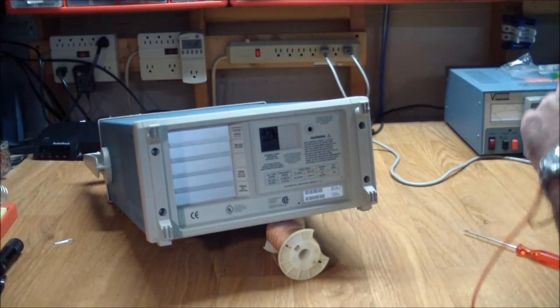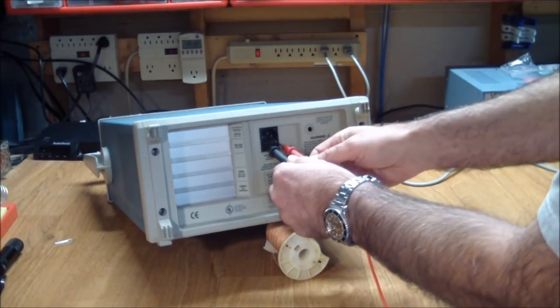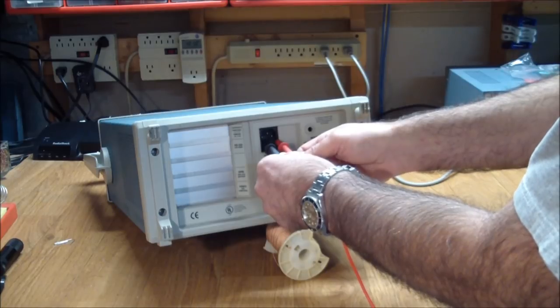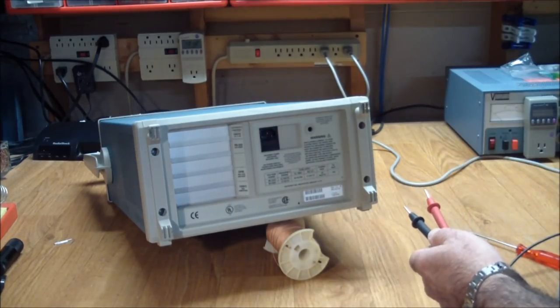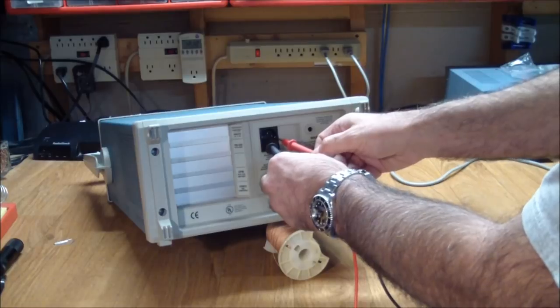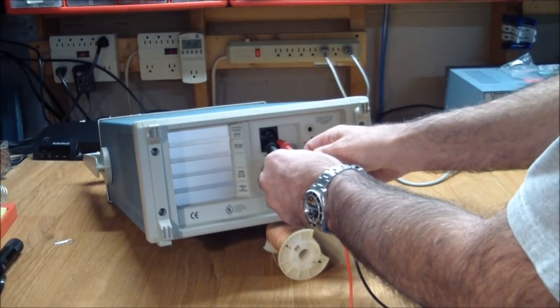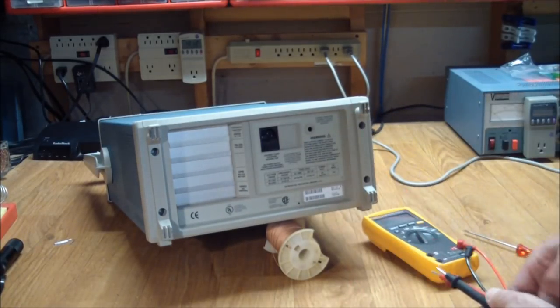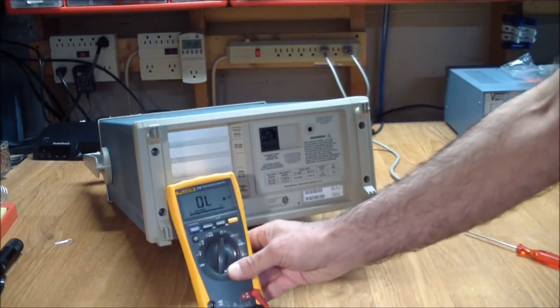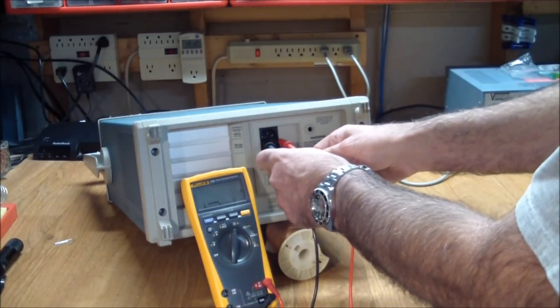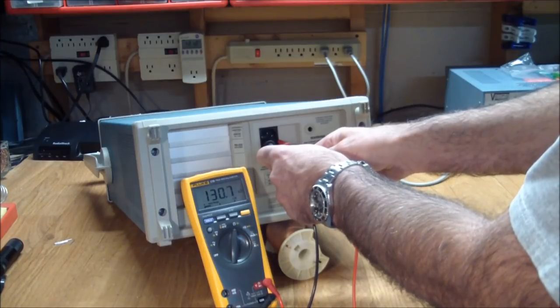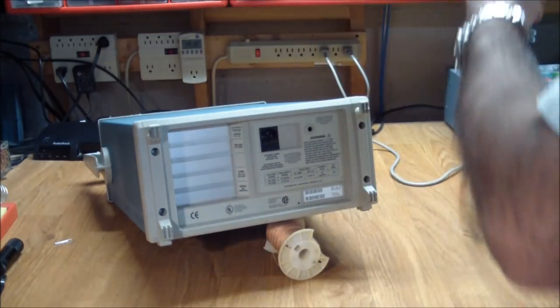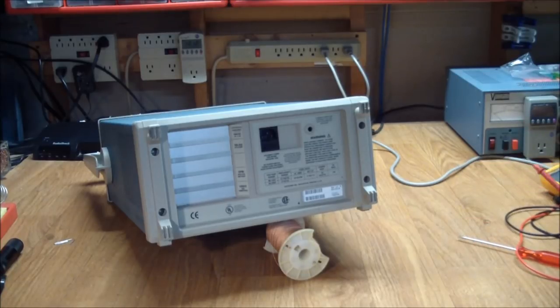So it does tell us that the fuse is good and is the correct value. Always do a quick short check by touching the neutral on the hot inputs even though that's not going to tell us a whole lot right now. So let's put the fuse back in. Okay there's no short and if we actually do a resistance test it shows 130k. So there's no short at least not on the primary side.